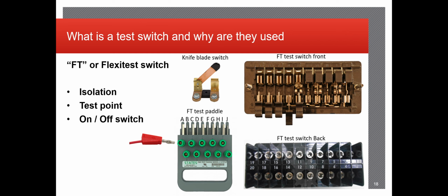This is primarily used for testing purposes, actually, not as much a safety example, other than something I'll discuss in a bit. But it's really useful for testing, because if the client wants a relay to be tested without any other equipment being taken out, it's very easy to, for one, isolate the relay just by utilizing the test switches. If we had to unwire all the contacts on the relay that were hot and isolate them that way, that could lead to a lot of dangerous situations, such as electric shock or misoperating of equipment. So the test switches are really nice.